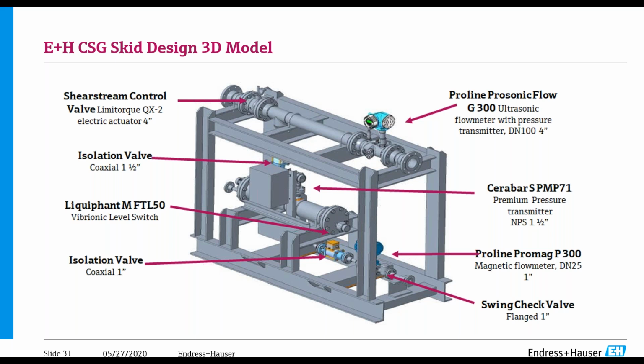So the benefits that we have on the Prosonic G300 are, first of all, the material of construction. The transducers themselves are made out of titanium, which is obviously a good material for abrasive applications. But even through design, we've taken into account this abrasive situation that we need to manage inside the flow meter, and we've actually recessed the transducers.